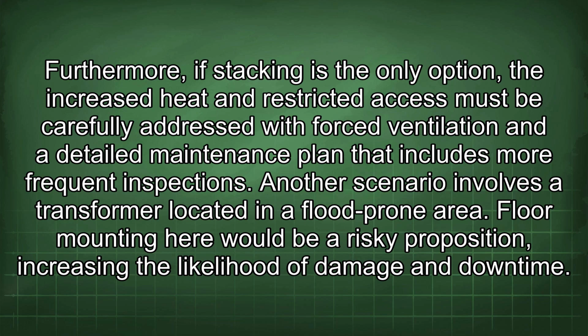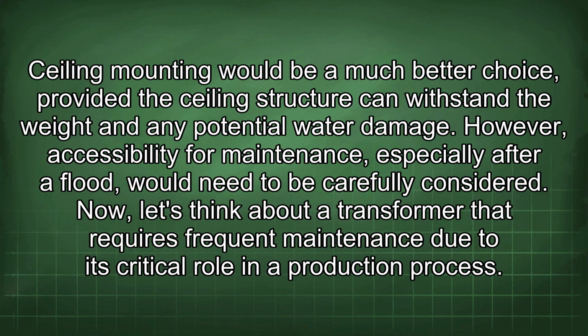Another scenario involves a transformer located in a flood-prone area. Floor mounting here would be a risky proposition, increasing the likelihood of damage and downtime. Ceiling mounting would be a much better choice, provided the ceiling structure can withstand the weight and any potential water damage. However, accessibility for maintenance, especially after a flood, would need to be carefully considered. Now, let's think about a transformer that requires frequent maintenance due to its critical role in a production process.